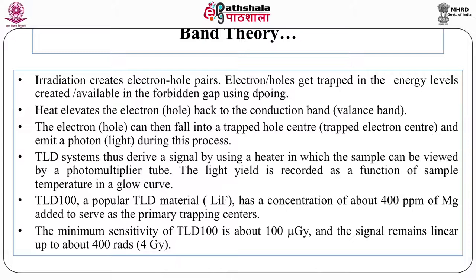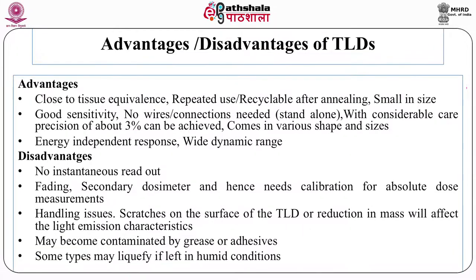There are many TL materials. TLD-100 is a popular TLD material based on lithium fluoride with about 400 ppm magnesium added as a primary trapping center. Its detection sensitivity is about 100 microgray. Disadvantages of TLDs include no instantaneous readout, fading (requiring calibration), need for calibration for absolute dose measurements, and handling issues — scratching on the surface may reduce mass or response, and contamination by grease or adhesive can change its response.